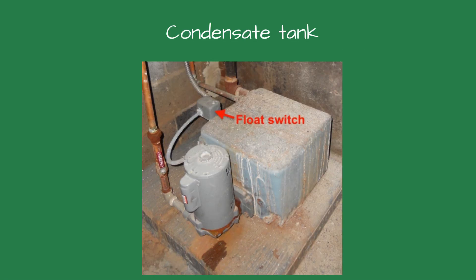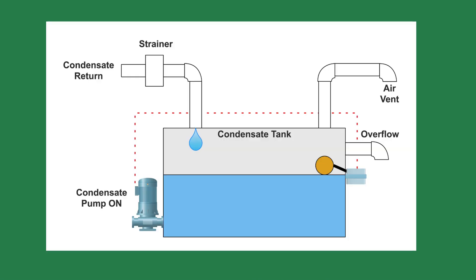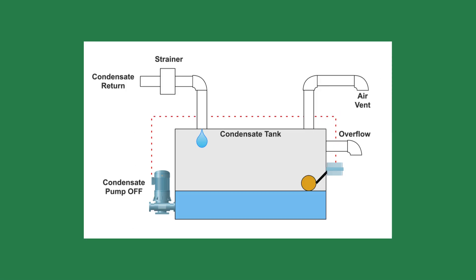The condensate tank is typically much smaller than a boiler feed tank. Inside the tank is an internal float that controls the pump operation. As the water level rises in the tank, the float switch starts the pump and pumps the condensate. When the water level in the tank drops, the pump is switched off.